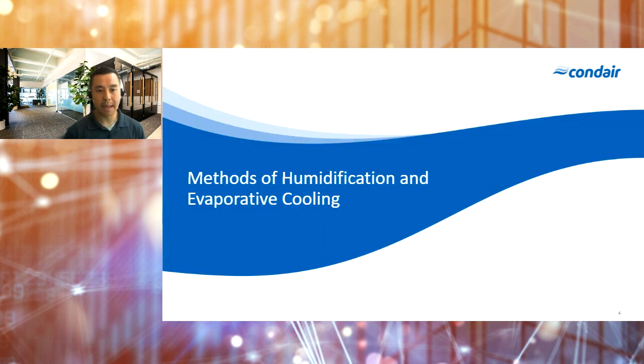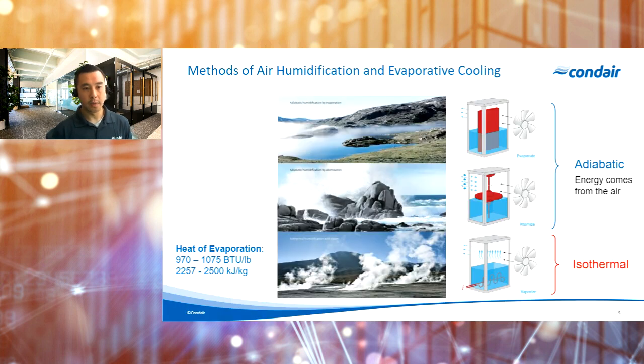So we'll start with methods of humidification and evaporative cooling. There are a couple of ways that we can humidify or cool the air, and the processes that we're going to look at here are what we refer to as the adiabatic process or an isothermal process. Keep in mind that in both processes, we're evaporating water into the air to increase that moisture content. The amount of energy needed is the same regardless of whether it's an adiabatic or an isothermal process. It's about 1,000 BTUs per pound of water evaporated. That is really the energy needed to drive the phase change between liquid water and vapor.